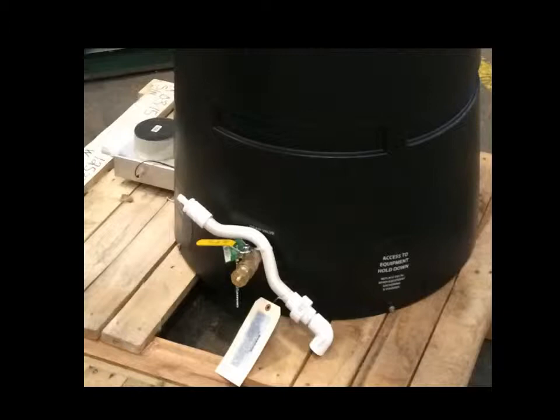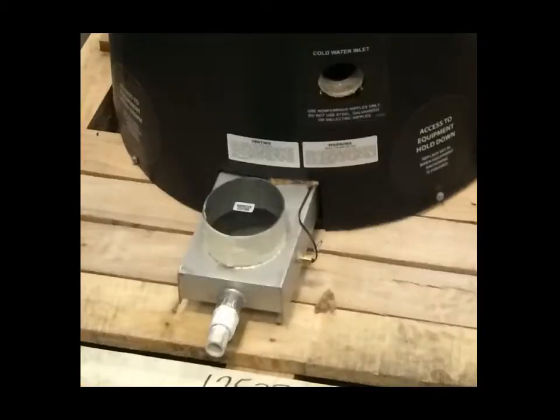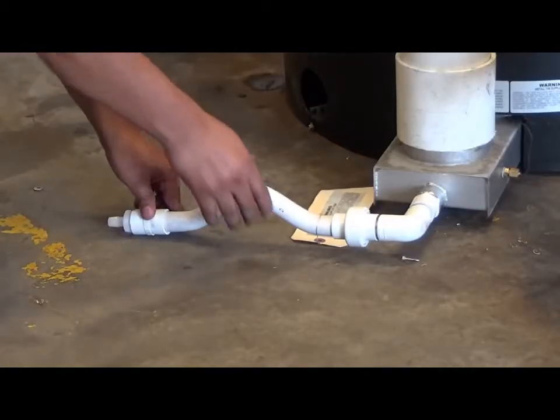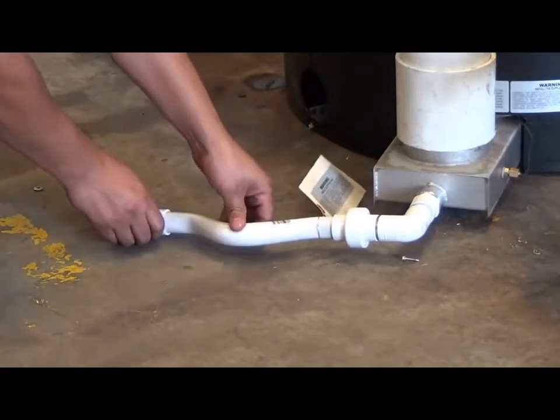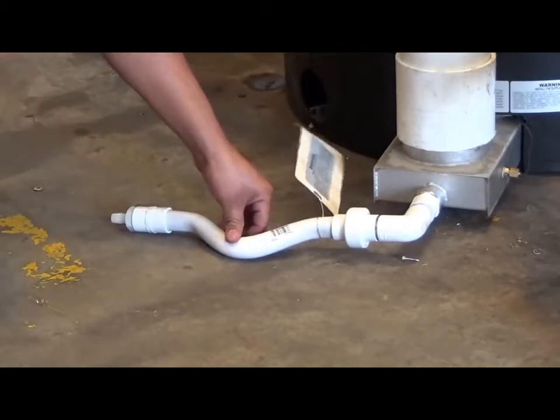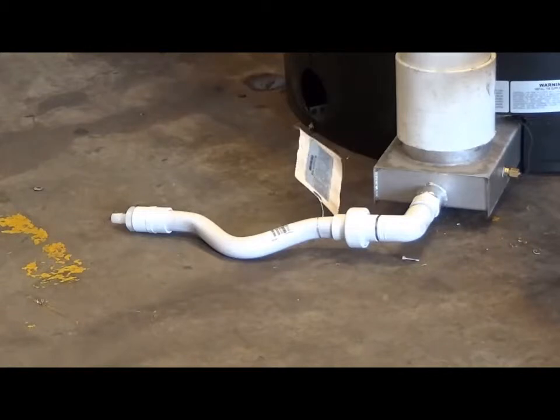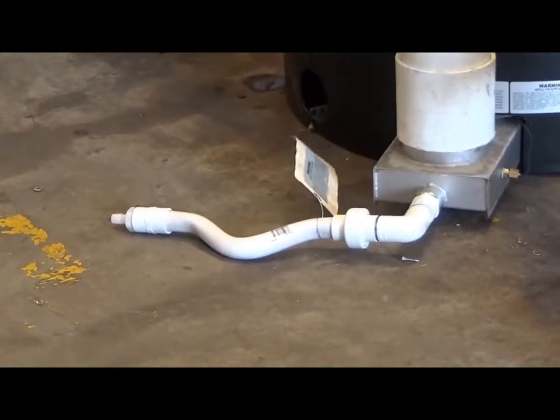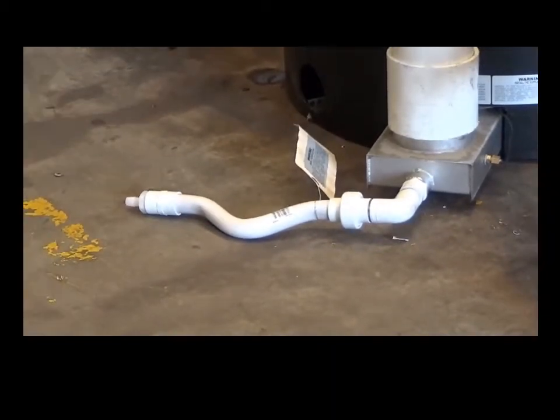A condensate trap ships with the unit and must be installed on the condensate drain to prevent flue gases from escaping and creating a hazardous condition in the installed space. The condensate drain is located on the flue outlet at the bottom of the water heater. Connect the condensate trap assembly to the PVC fitting on the flue outlet. Then, rotate the trap so that it contacts the floor. Connect a condensate drain line or an optional condensate neutralization system to the trap assembly.